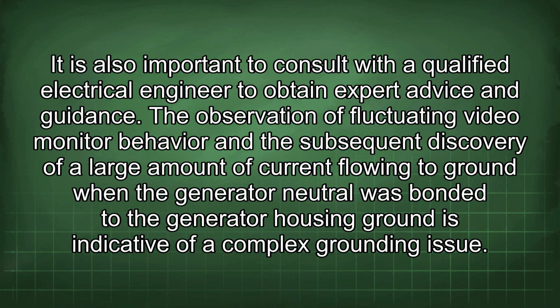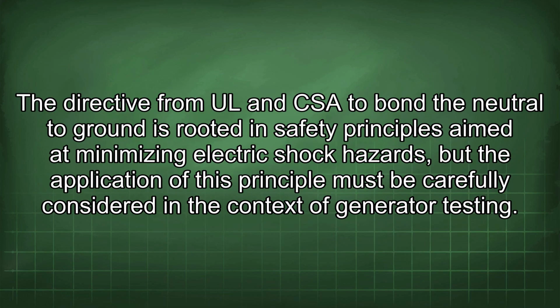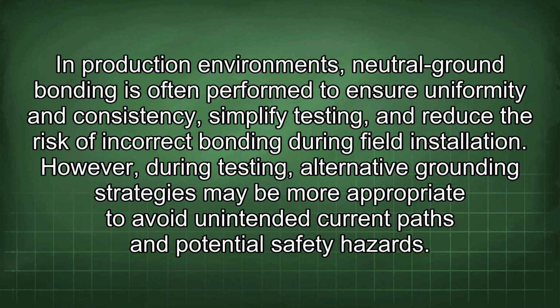The observation of fluctuating video monitor behavior and the subsequent discovery of a large amount of current flowing to ground when the generator neutral was bonded to the generator housing ground is indicative of a complex grounding issue. The directive from UL and CSA to bond the neutral to ground is rooted in safety principles aimed at minimizing electric shock hazards, but the application of this principle must be carefully considered in the context of generator testing. In production environments, neutral ground bonding is often performed to ensure uniformity and consistency, simplify testing, and reduce the risk of incorrect bonding during field installation. However, during testing, alternative grounding strategies may be more appropriate to avoid unintended current paths and potential safety hazards.